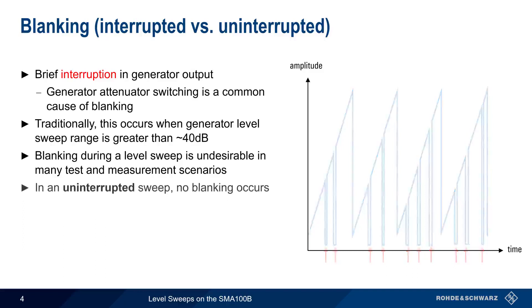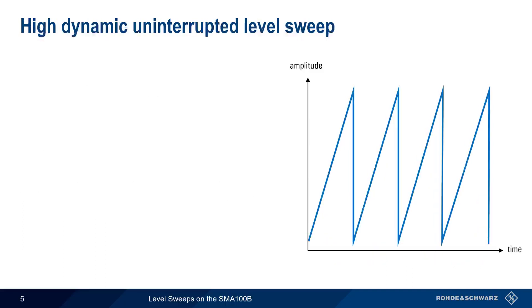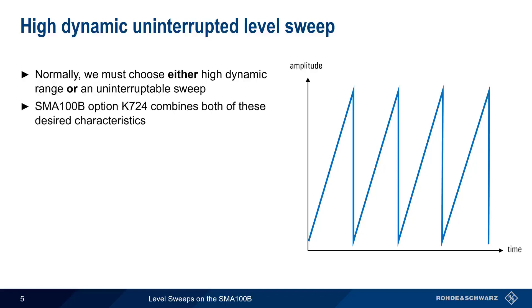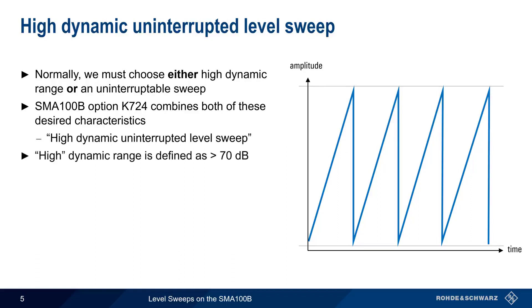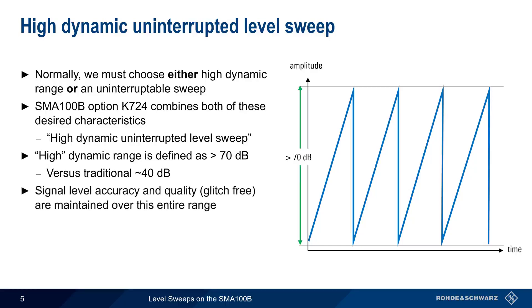Sweeps in which no blanking occurs are therefore called uninterrupted sweeps. Although normally we have to choose between either a high dynamic range or an uninterrupted level sweep, the SMA100B option K724 combines both of these desired behaviors. This option is therefore called high dynamic uninterrupted level sweep. In this case, high dynamic range is defined as being 70 dB or more versus the traditional max uninterrupted range of about 40 dB. The high dynamic uninterrupted level sweep option maintains level accuracy and signal quality, that is no glitches or dropouts, over the entire level range.